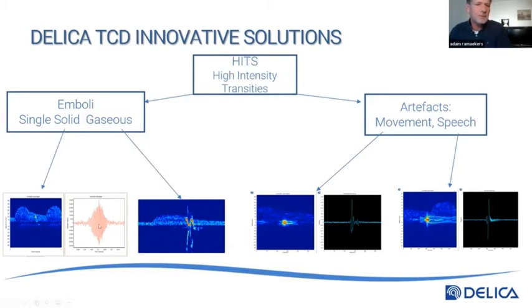It's a zero crossing line, very stable, very frequent. You see the emboli over here, and here you see a gaseous one which moves around the vessel completely. And on the other side, you see two kinds of artifacts: movement artifacts, which have a completely different pattern, and also a speech artifact. Of course, there are also other artifacts. Think about, especially during surgery, when diathermy is used.